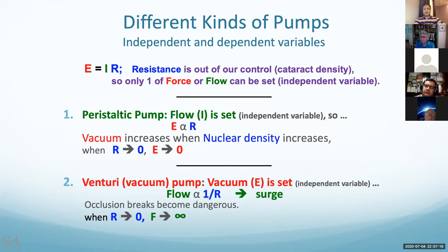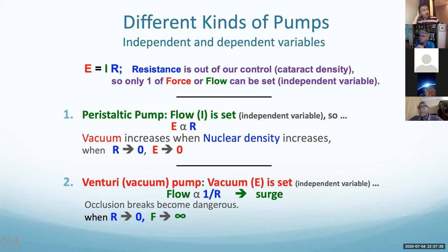Thank you, Steve, for this well-explained point. The frequent question is about the peristaltic pump versus venturi pump. The peristaltic vacuum means that the vacuum will build up after occlusion. So the equation tells you that vacuum becomes a function of resistance.